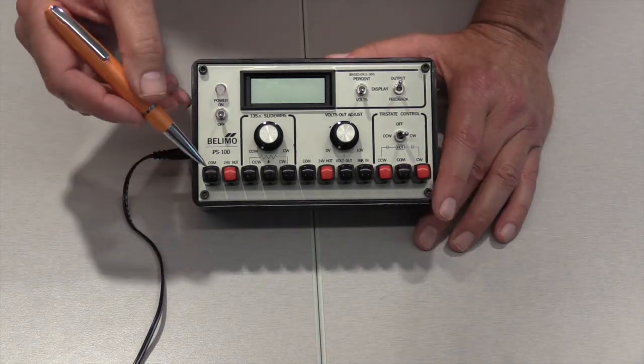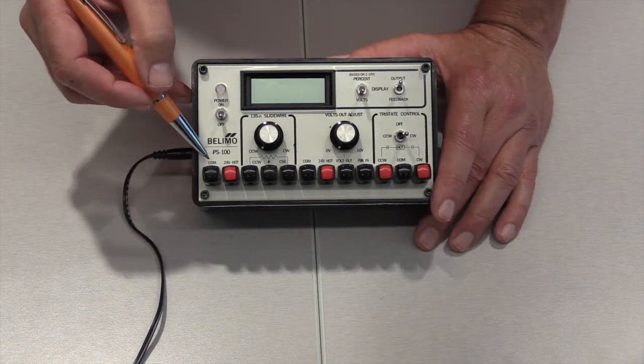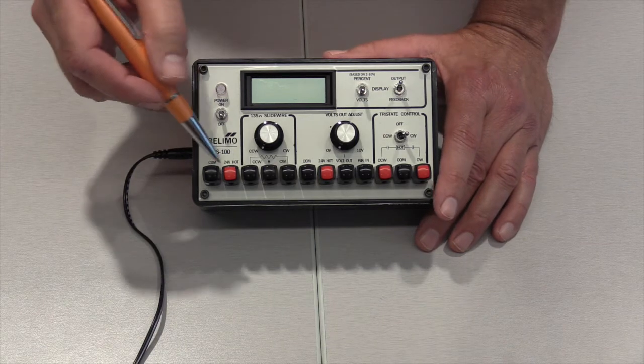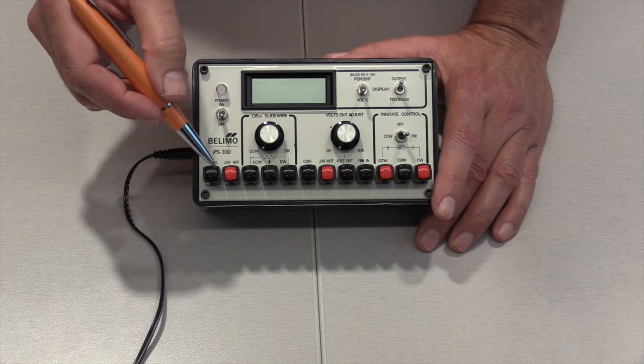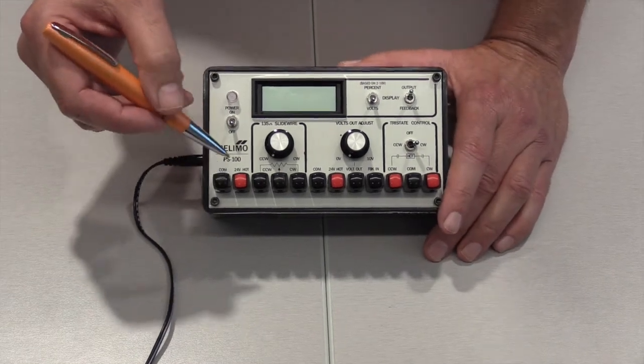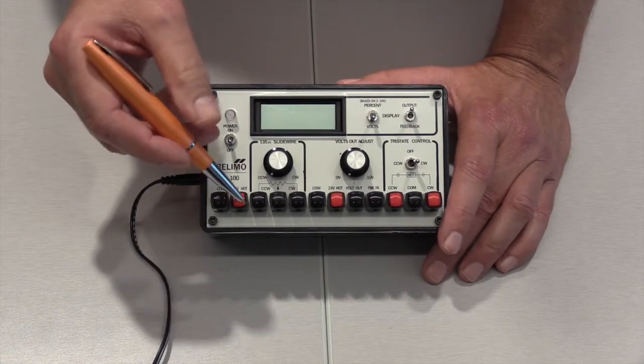Let's start with the first two posts right here and the very first one is a common. The very next one is a 24 volt hot and what that's for is this gives a constant 24 volt power out to the actuator and it's not changeable. It's a steady 24 volts.